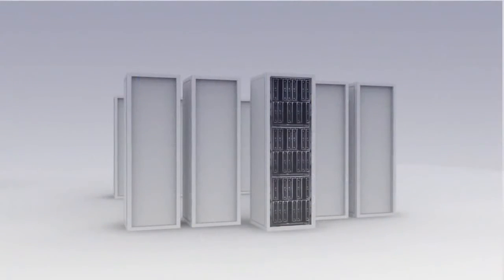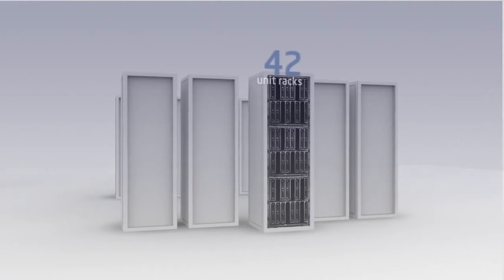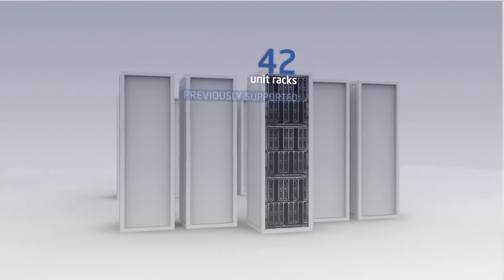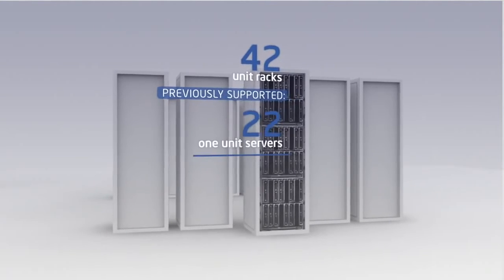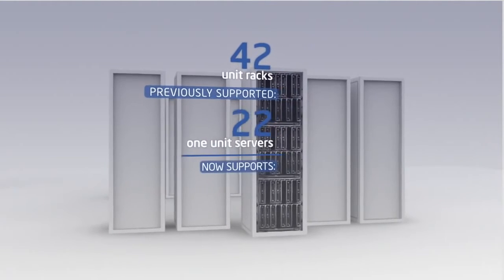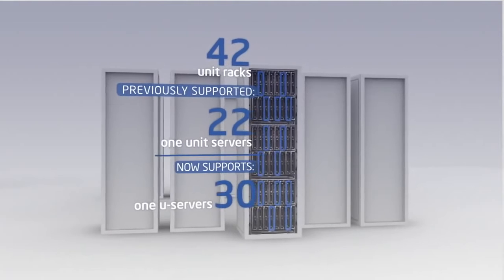For example, using Intel DCM, a 42-unit rack that previously supported 22 one-unit servers could now support up to 30 one-unit servers, delivering approximately 40% more processing power within the same power allowance and rack footprint.